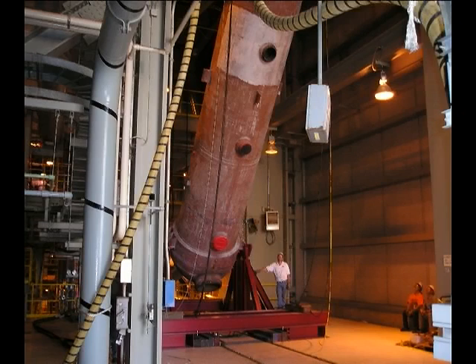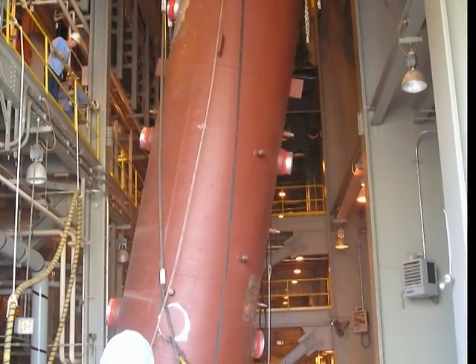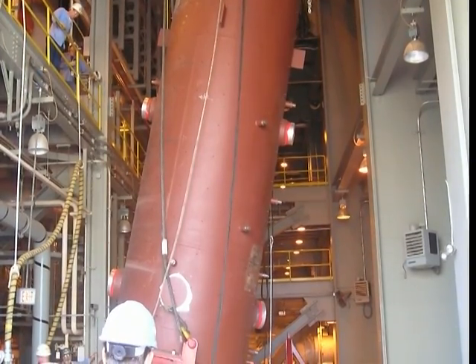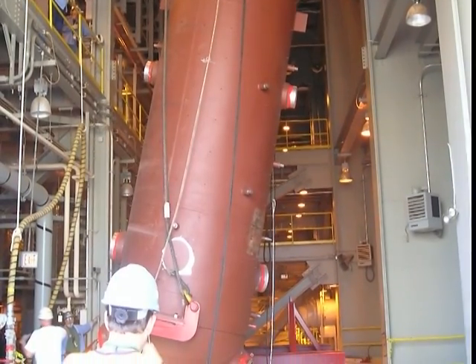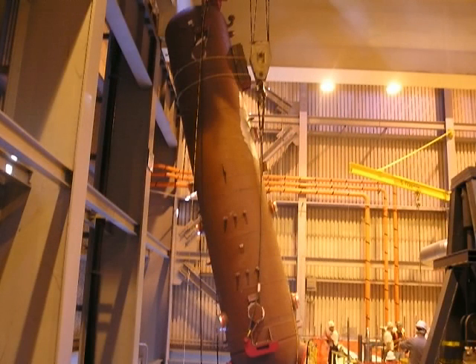The new vessel was rotated into a vertical position and lifted to the upper hoist limit. The auxiliary hoist was then rigged to the lifting brackets at the base of the unit. Upon rigging the new feedwater heater, it was rotated to 23 degrees from its vertical position and trolleyed to the installation point. Once the bottom end of the new heater was over the access hole, the auxiliary hoist was lowered and the unit centered in the hole, and the auxiliary hoist rigging was removed.